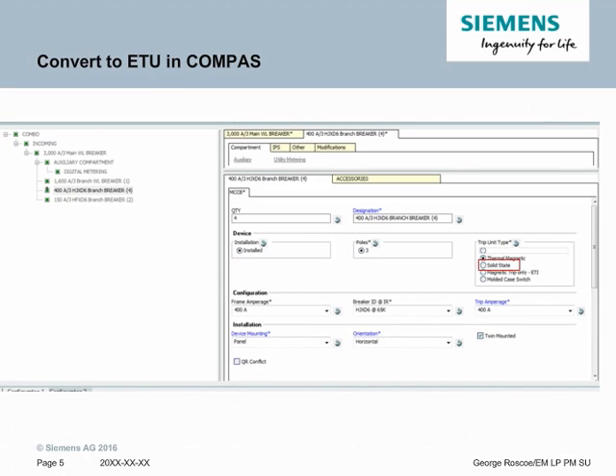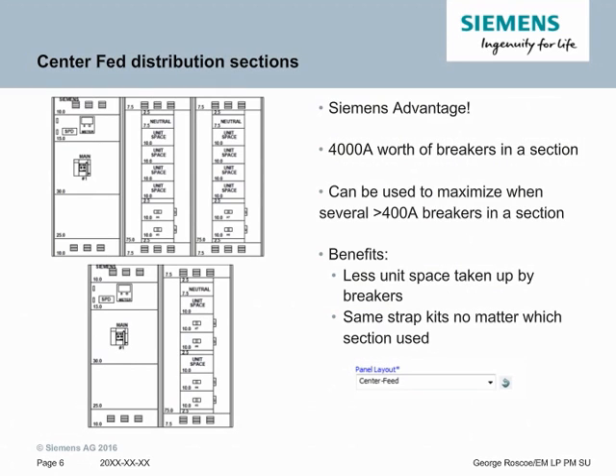Another key Siemens advantage versus the competition is center-fed distribution sections. These sections allow for up to 4,000 amps of breakers to fit in a single group-mounted distribution section. It can be used to maximize the number of breakers in a section, especially when there are several breakers that are 400 amps or greater. The key design feature is the bus connection comes in at the middle of the section. A center-fed panel can easily be discerned by finding the 2.5 inches of restricted space in the middle of the panel, as you can see in the bottom image.